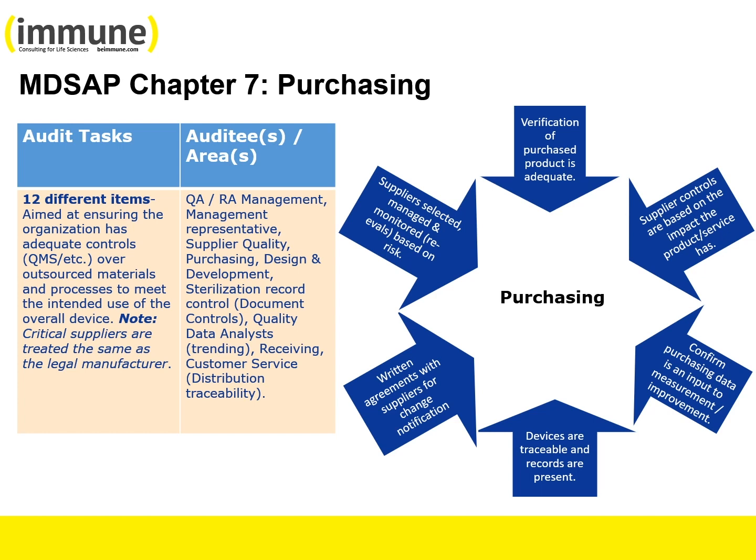meet the specified requirements, ensured the continued capability of suppliers to provide quality products that meet those specified requirements through reevaluations, determined and implemented an appropriate combination of controls applied to suppliers in conjunction with the acceptance verification activities performed in-house to ensure conformity to the product and quality management system requirements. This information should be based on the impact of the supplied product on the finished medical device.